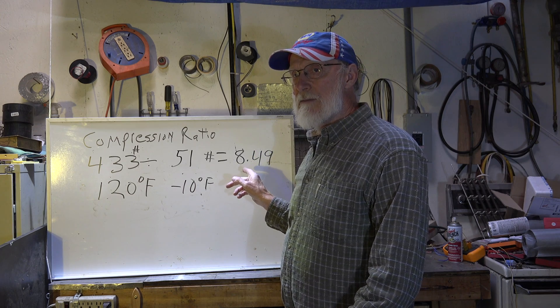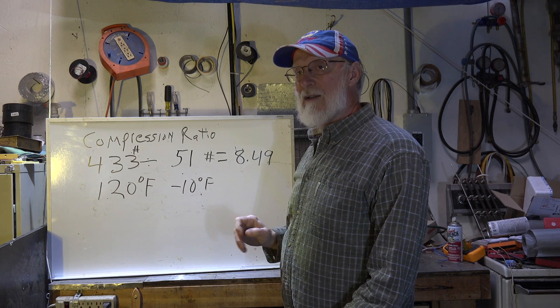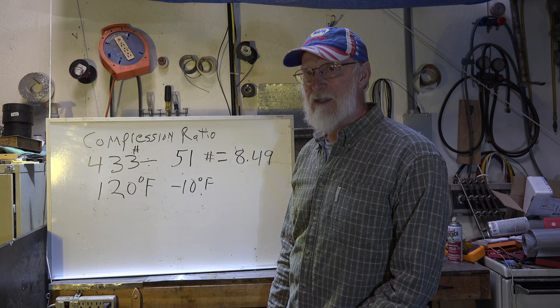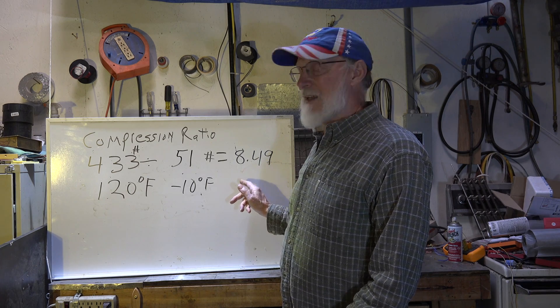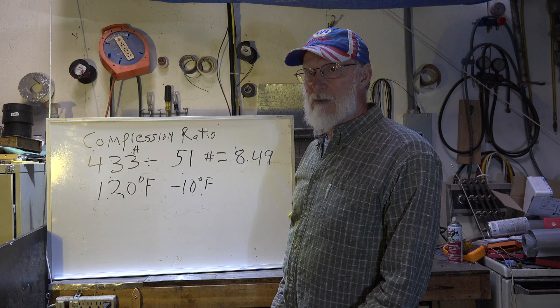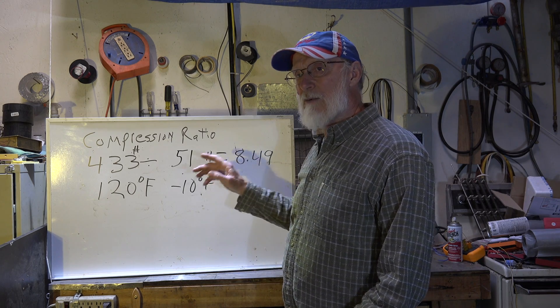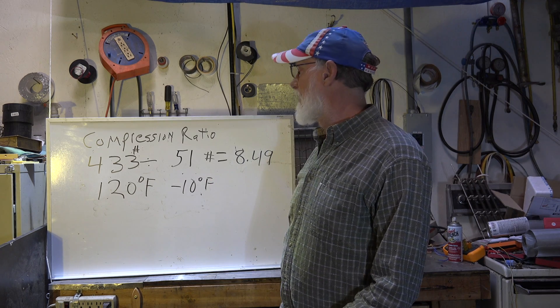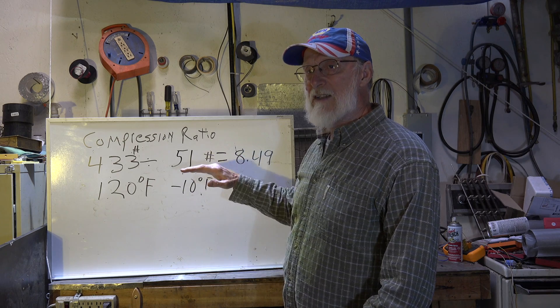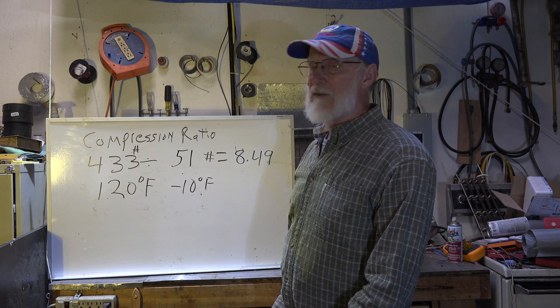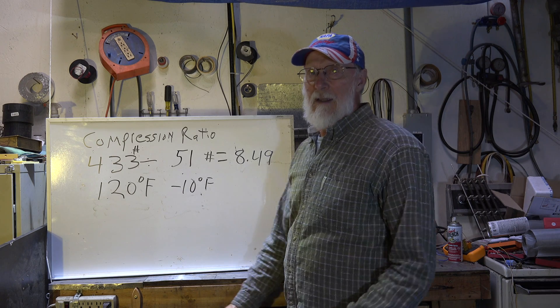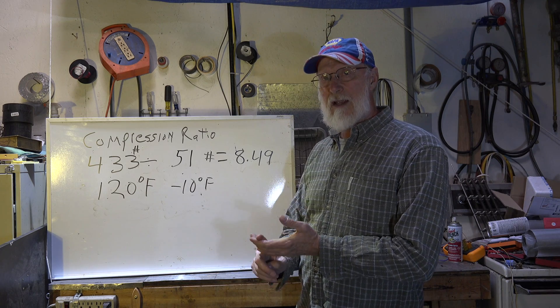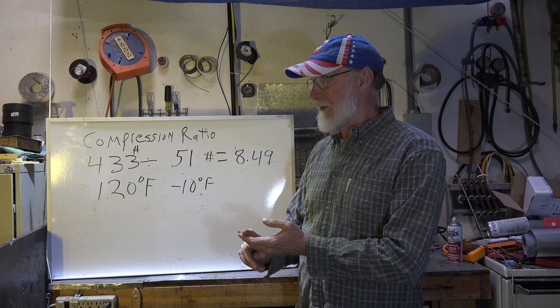The higher the number, the less it pumps. So this is going to be a lot less capacity — that compressor is not going to have anywhere near the capacity it had when we had the higher suction pressure. The reason for that is re-expansion of gas. That high compression ratio is reducing the effective refrigerating effect of the refrigeration system.